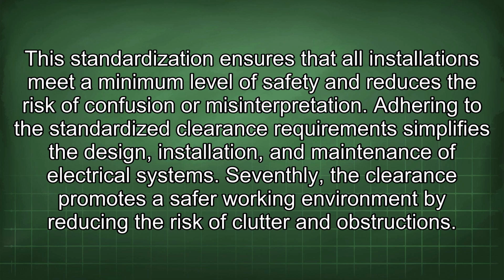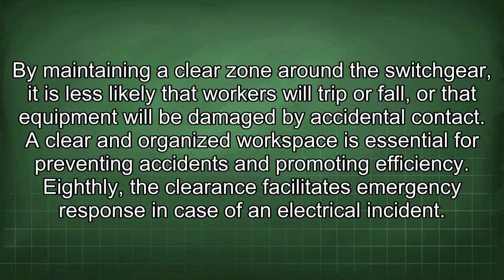Adhering to the standardized clearance requirement simplifies the design, installation, and maintenance of electrical systems. Seventhly, the clearance promotes a safer working environment by reducing the risk of clutter and obstructions. By maintaining a clear zone around the switchgear, it is less likely that workers will trip or fall, or that equipment will be damaged by accidental contact. A clear and organized workspace is essential for preventing accidents and promoting efficiency.